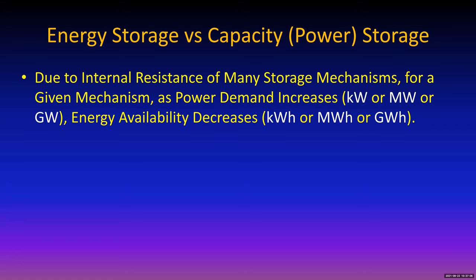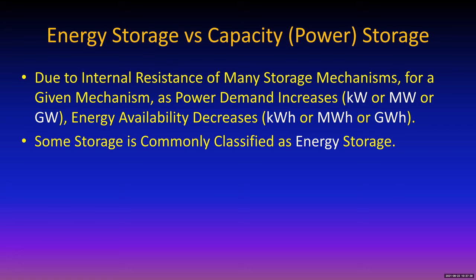A typical small energy storage system, a 10 kilowatt hour system, will provide about 3,900 watts. Beyond that, it cuts back, because after that point, the losses in the battery system are unjustifiably large. So storage systems are rated by their energy and their power ratings, and that's important in terms of the design process.